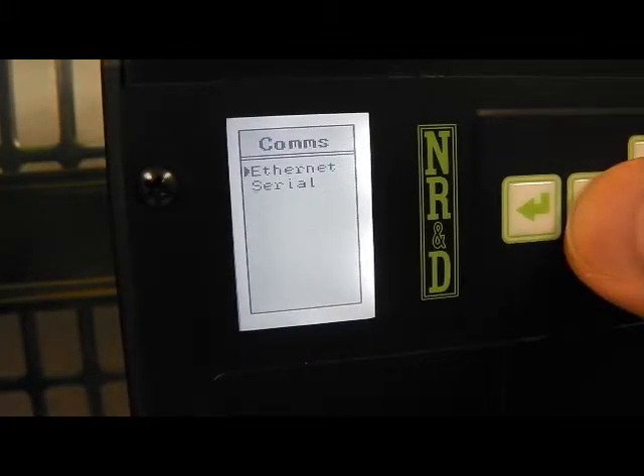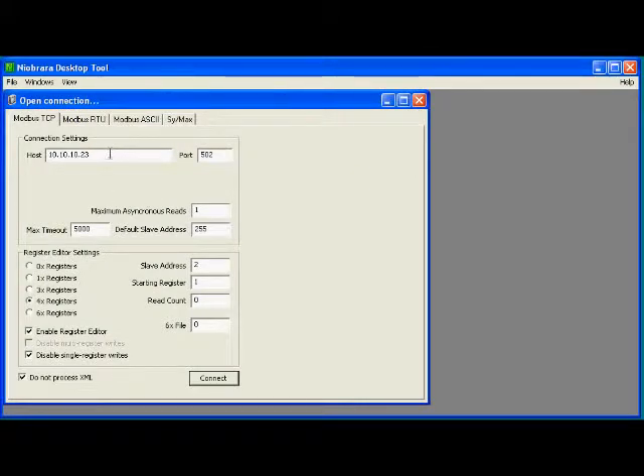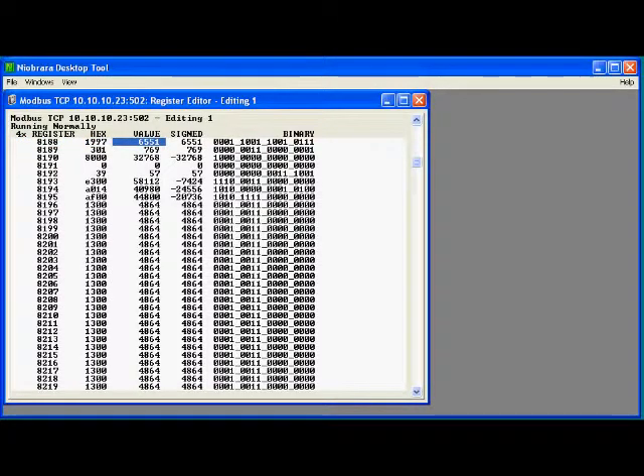We will use NRD tool to demonstrate Modbus TCP connections. Open a new connection to the IP address of the DEB. Select 4X for the register type. The slave address for the model 655 is 1. Now we see the registers in the PLC. Looking at register 8188 shows the PLC type as a model 655.